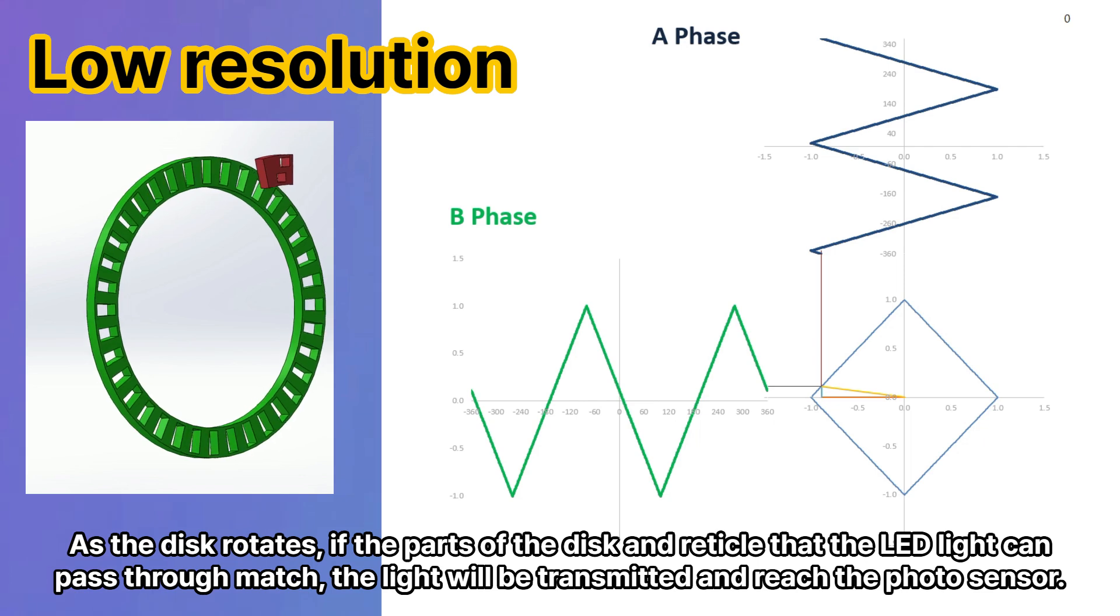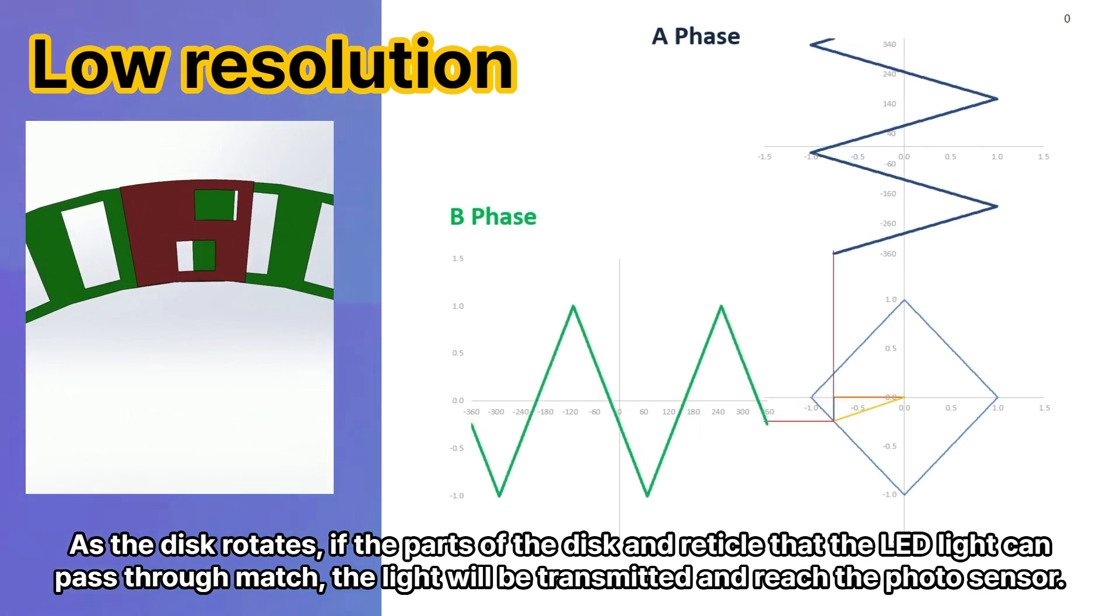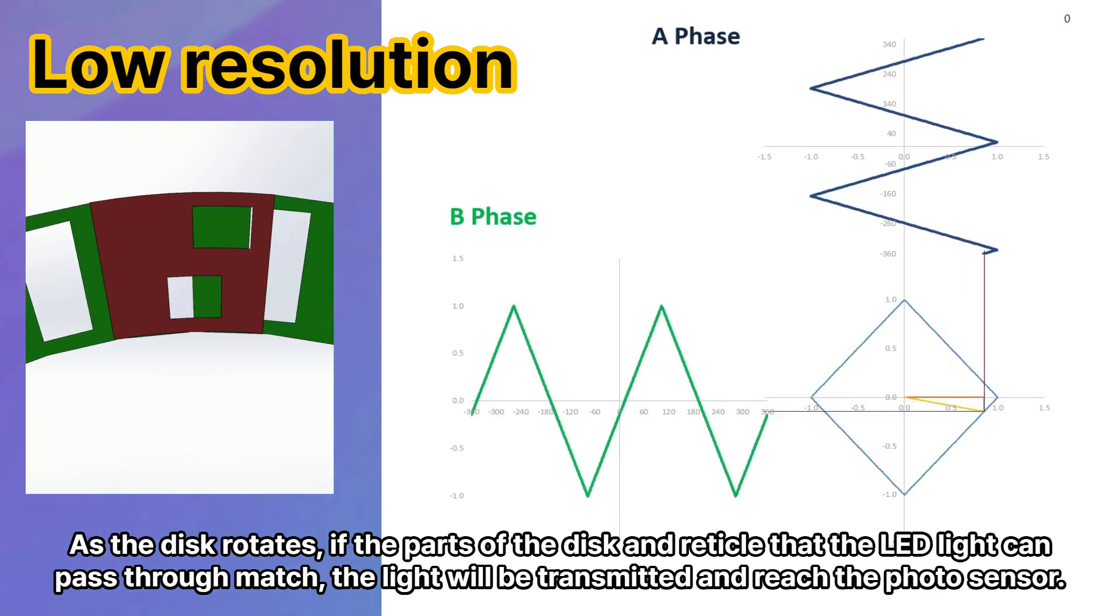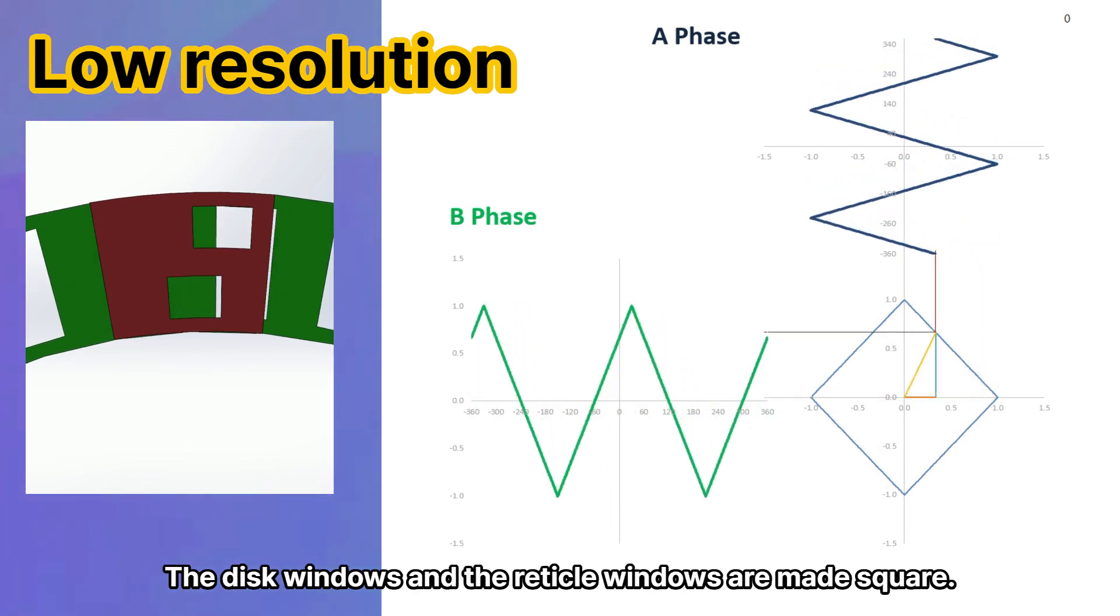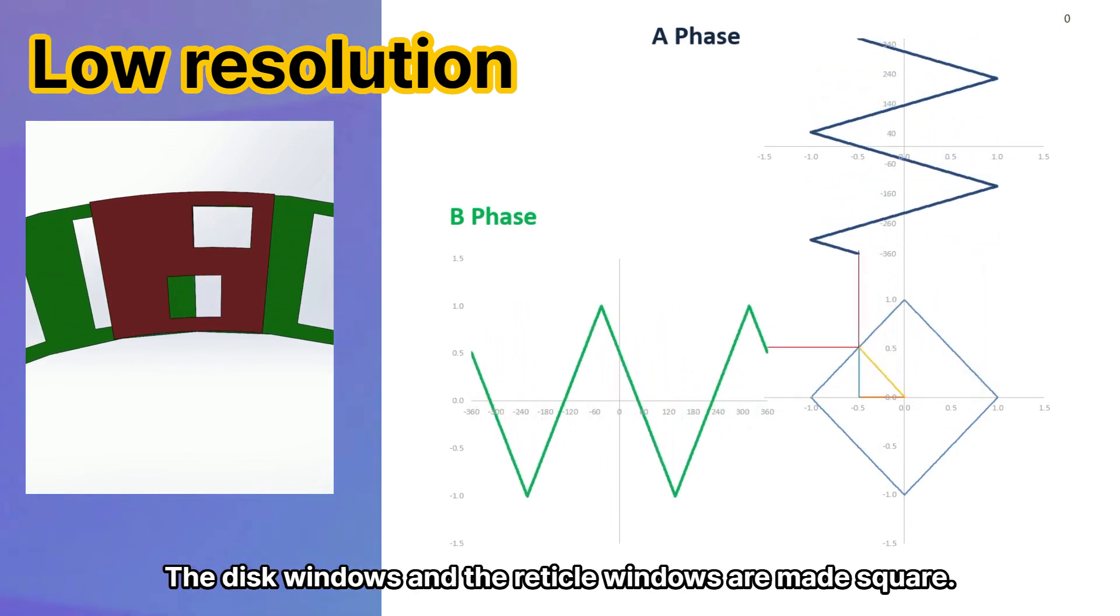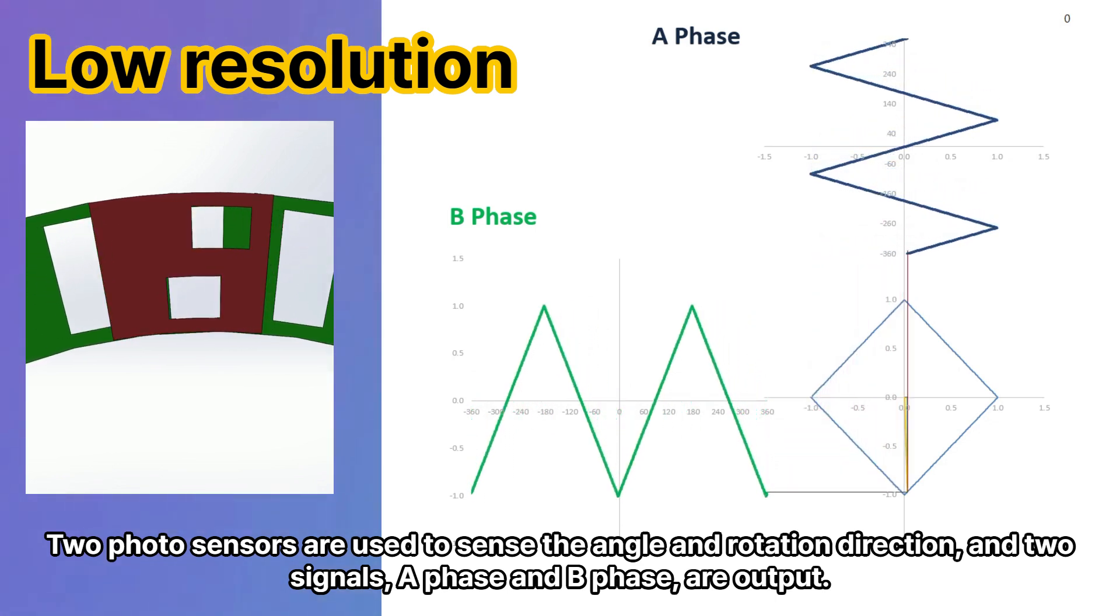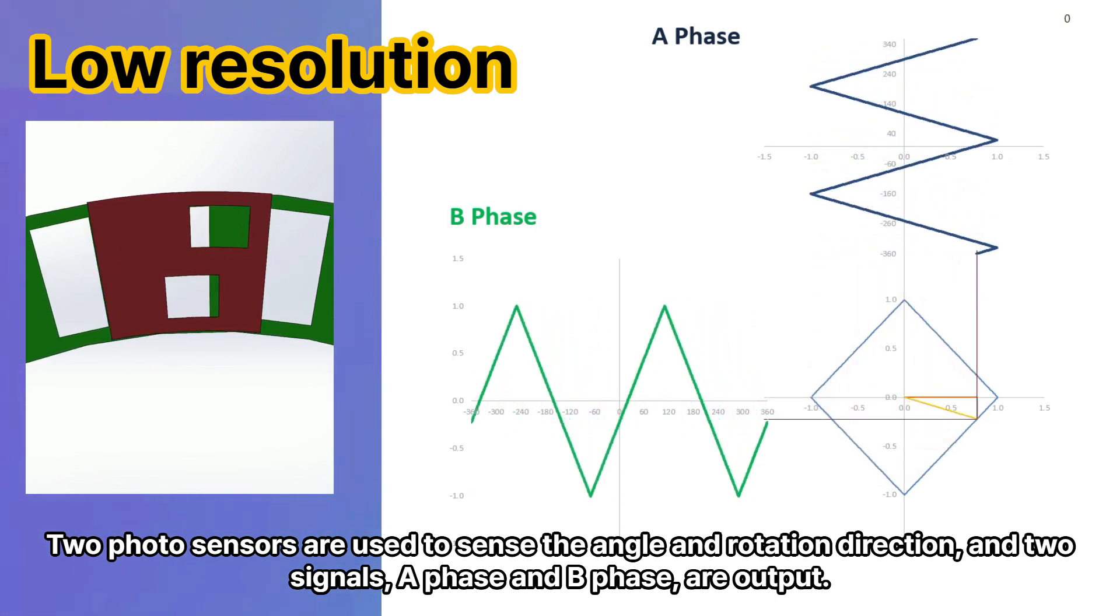As the disk rotates, if the parts of the disk and reticle that the LED light can pass through match, the light will be transmitted and reach the photosensor. The disk windows and the reticle windows are made square. Two photosensors are used to sense the angle and rotation direction, and two signals, A phase and B phase, are output.